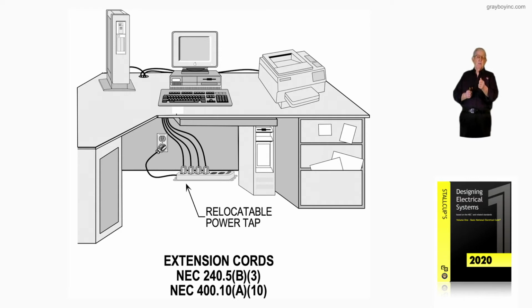Electricians just say, well, when I put an amp probe back at the panel on the branch circuit that has all these outlets on it, am I within 80%? Am I within 20 amps? Or am I a little over 20 amps and overloading that circuit? Now, 70B and Chapter 17 says that if you're a maintenance electrician, that's how you check it. And you want to make sure that you don't allow so many outlets on a circuit and allowing items to be plugged in that it will trip it.